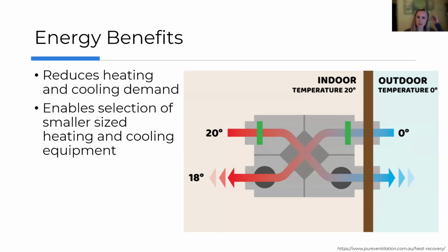Example: imagine we're in a heating dominant climate, like Minnesota where I'm from, in the winter. Imagine the indoor air temperature is about 20 degrees Celsius and the outdoor temperature is about 0 degrees. As warm indoor air is extracted and passes through the heat exchanger, its heat is transferred to the incoming cold air. It's not mixed, it's essentially just transferred over to pre-temper it. This process warms the fresh air supply to about 18 degrees, assuming the recovery unit operates at about 90% efficiency. Compared to simply opening a window and letting in unfiltered 0-degree air, the difference is pretty dramatic.